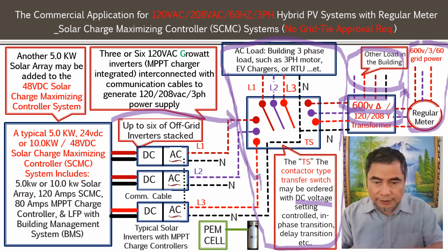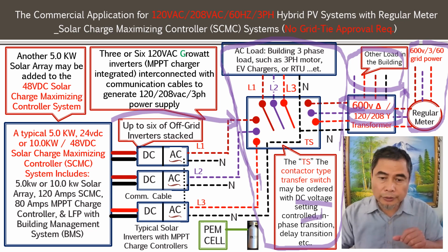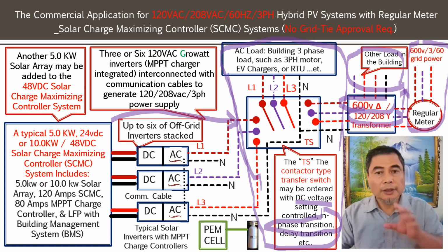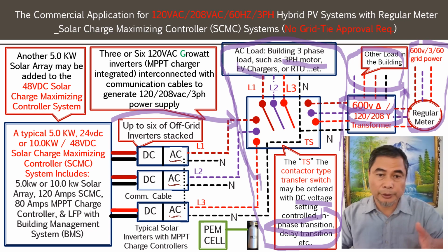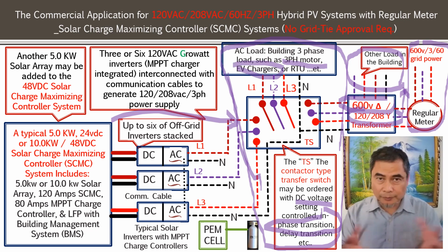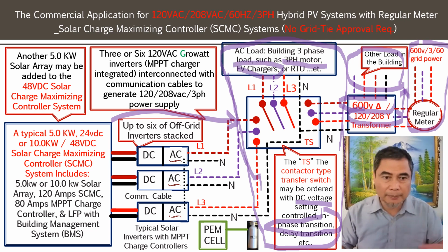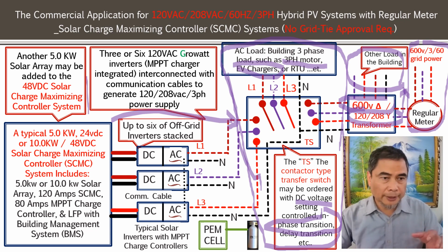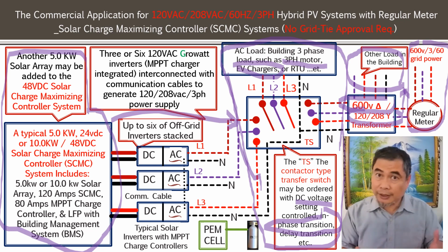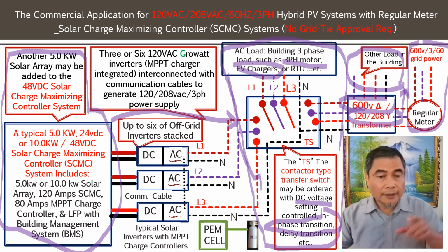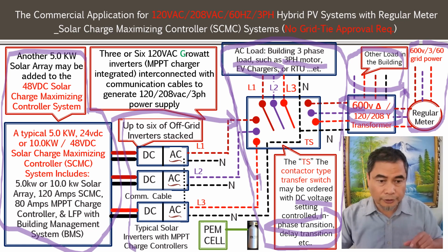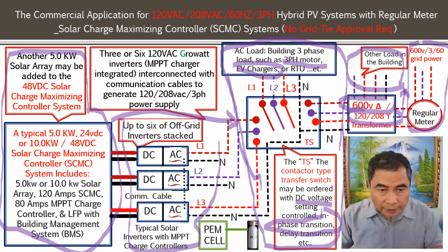So when you order that transfer switch, make sure you have in-phase transition control, especially when you have some kind of three-phase motor. And of course, you can have an EV charger built into the system. In a commercial building, you have the whole system set up, and that solar array would be on the roof. This solar array can be up to 20 kilowatts, and you can have up to 6 of these inverters.